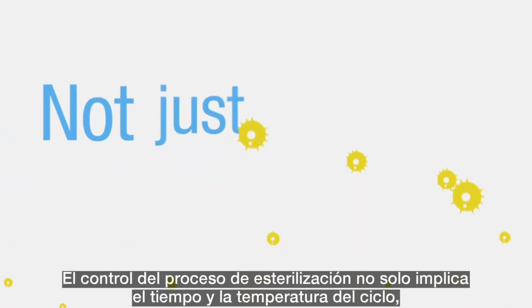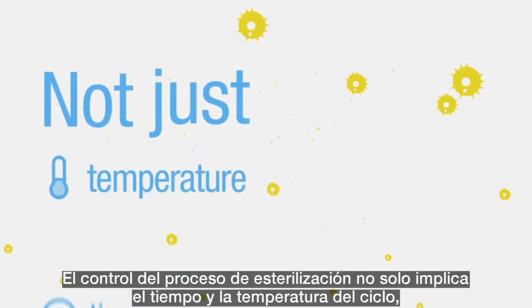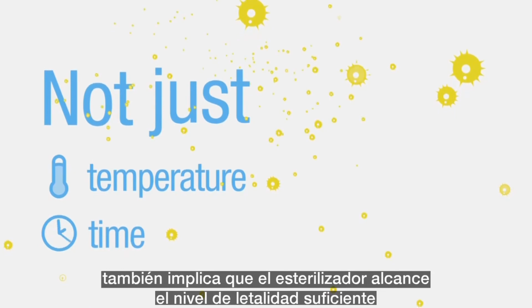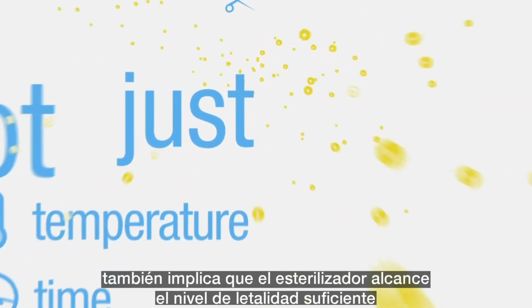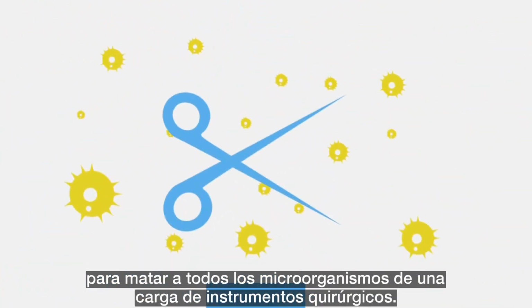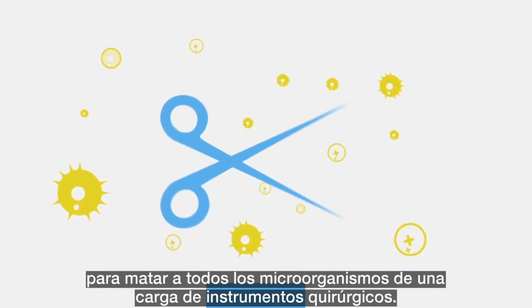Sterilization process monitoring is about more than cycle temperature and time. It's about whether or not your sterilizer successfully delivered enough lethality to kill all the microorganisms in a load of surgical instruments.